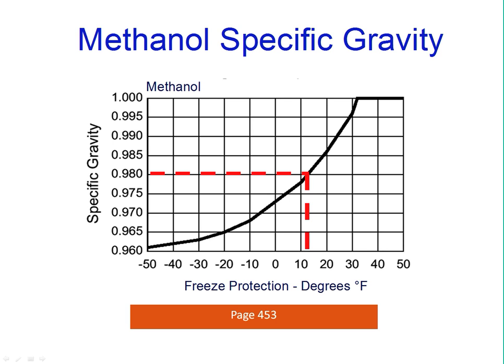In our flow controller IOM, you're going to find the conversion tables for the specific gravity for ethanol, methanol, and propylene glycol. Please keep in mind that the hydrometer for the glycol is different than that used with the alcohol. So on that previous slide you saw we were approximately 0.982. And if you read over from 0.982 to that slope and then drop down, you're going to see that that solution has a freeze protection of probably somewhere around 12 or 13 degrees.